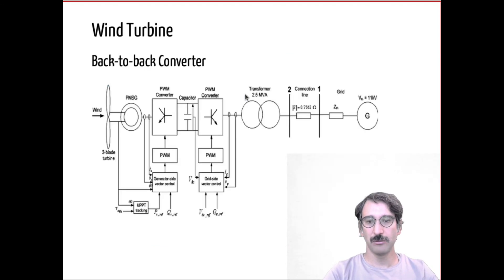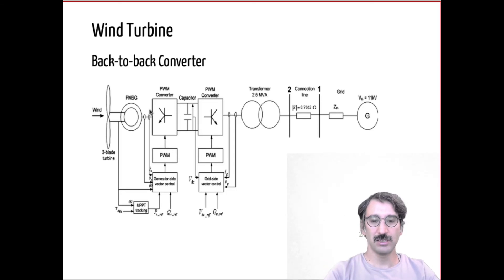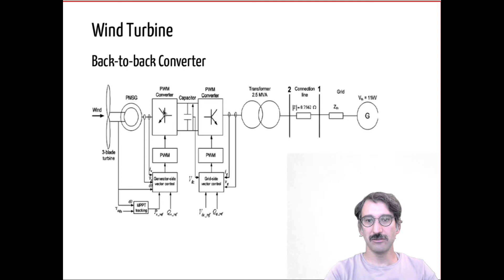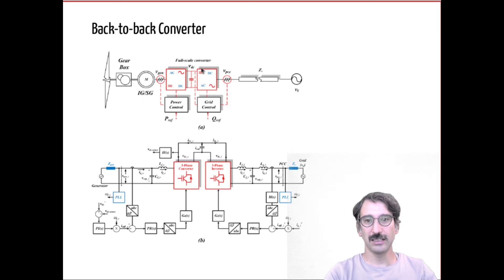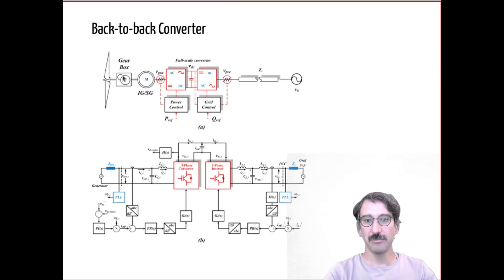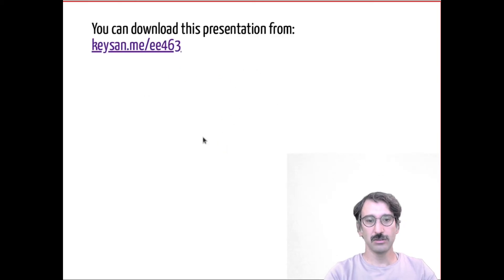Let's look at what's inside a wind turbine. The blades drive a permanent magnet synchronous generator or induction generator, producing variable-frequency three-phase AC that does not match the grid frequency. First, that AC is converted to DC — acting as a rectifier — and then that DC is converted to constant 50 Hz AC and sent to the grid. This is called a back-to-back converter arrangement: one AC-to-DC converter and one DC-to-AC converter, taking the variable-frequency voltage and delivering power at constant grid frequency.